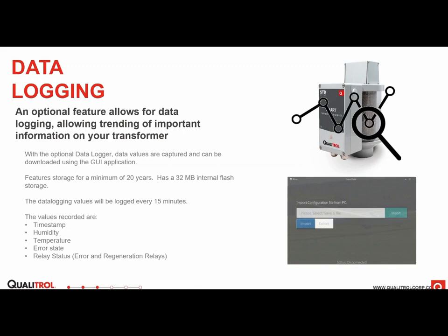So our data logger will log all of the values that are in the breather's firmware. It takes a timestamp, and it records the humidity, the temperature, the error state, and the relay status. The error state is dependent on all of the parameters: the RH, making sure all the sensors are working, all the communications are working. And then it will also let you know if it's in a regeneration mode, a post-regeneration or a cooling mode. It records all of that. It records every 15 minutes and can store for over 20 years.